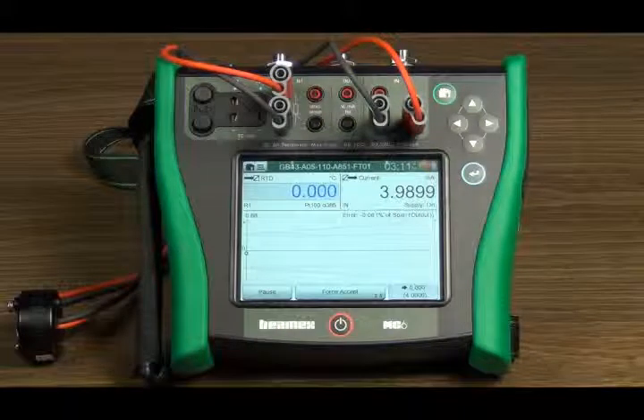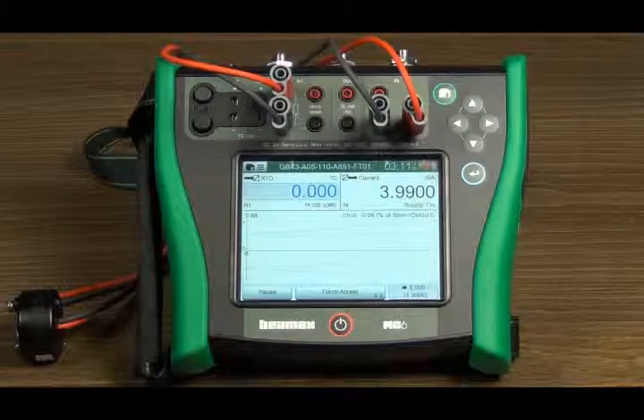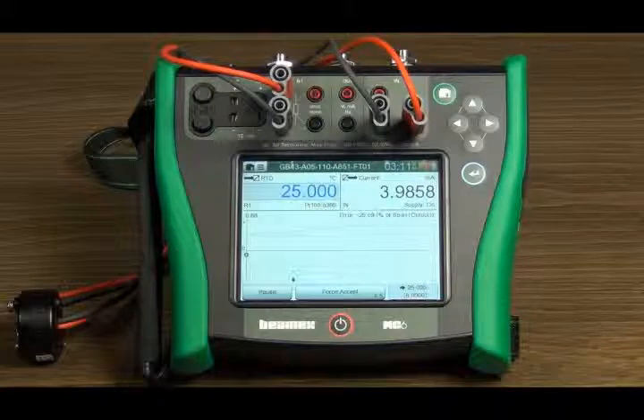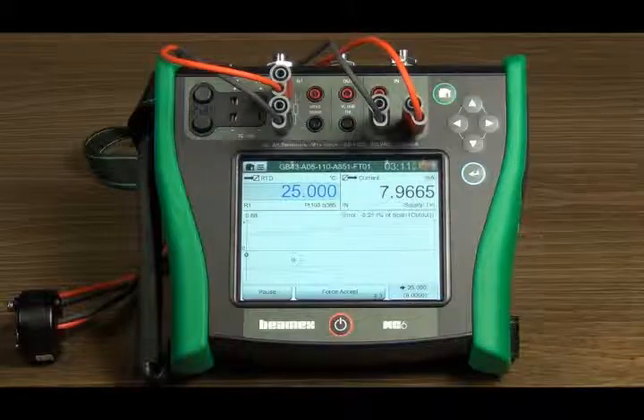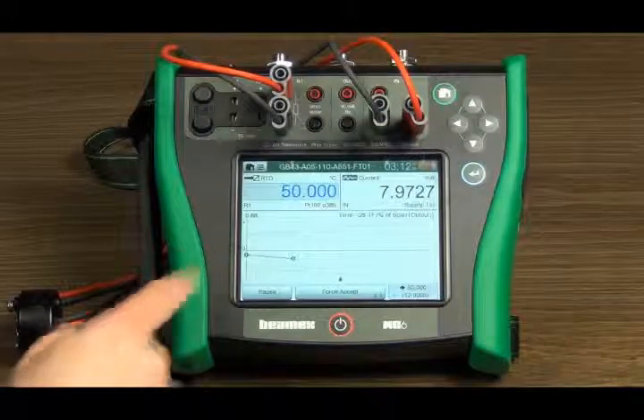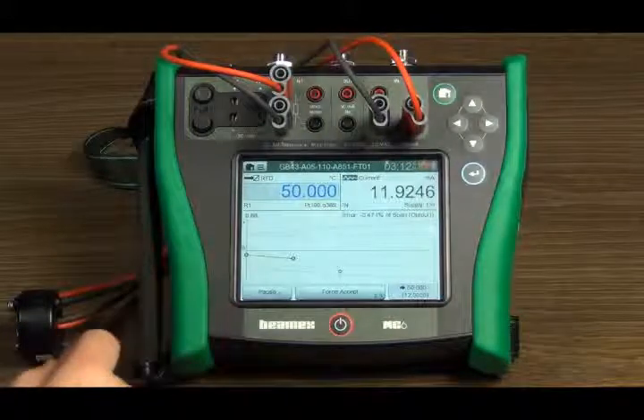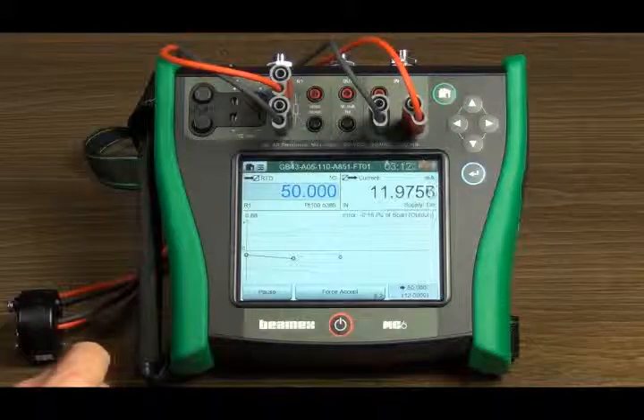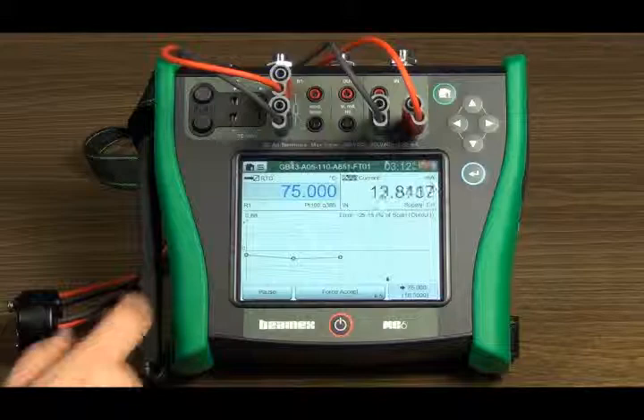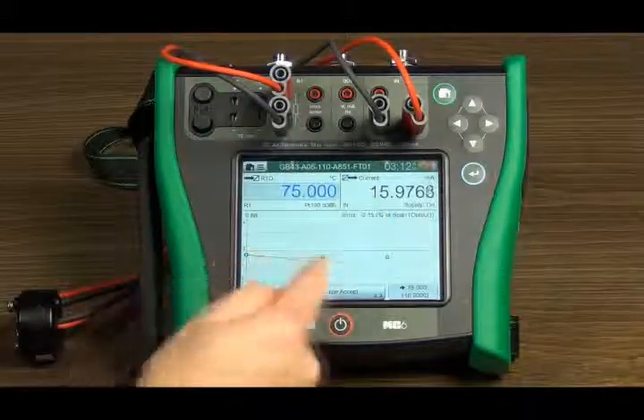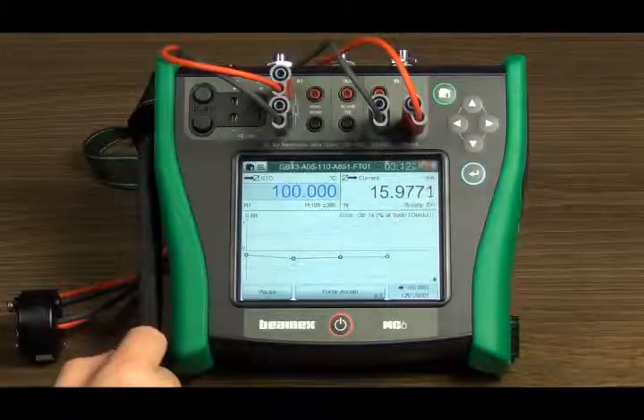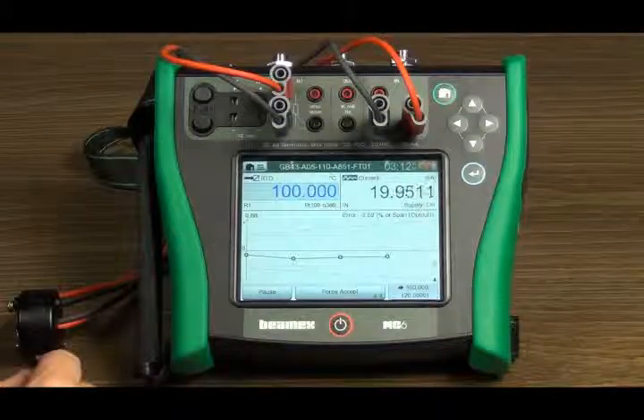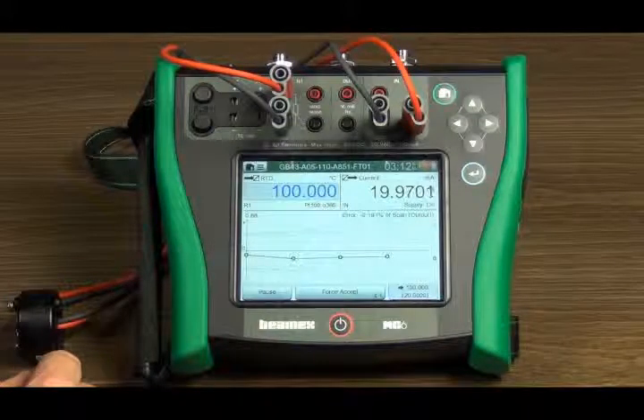As the automatic calibration proceeds, the error graphics will begin to expand. The error line will remain green as long as the error is within the limits. It will turn red if the error limits are exceeded. The blue lines in the graphics are the acceptable error limits. After calibration, the device will indicate whether the calibration was a pass or fail.